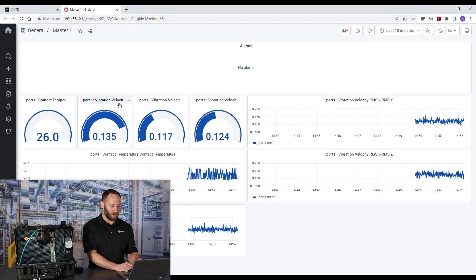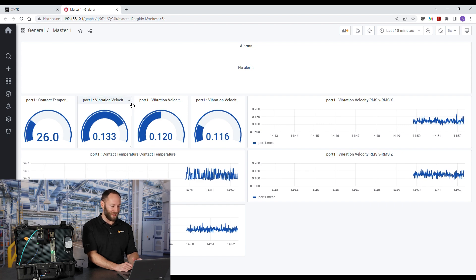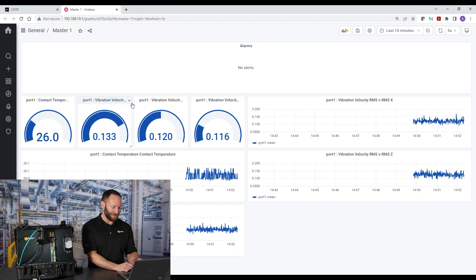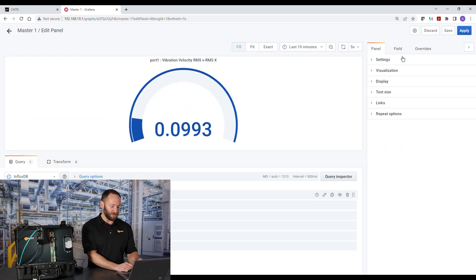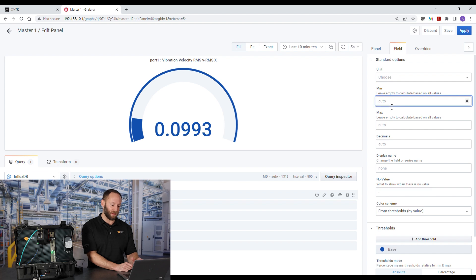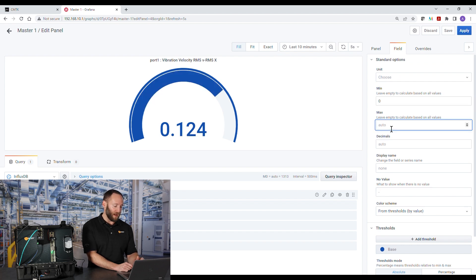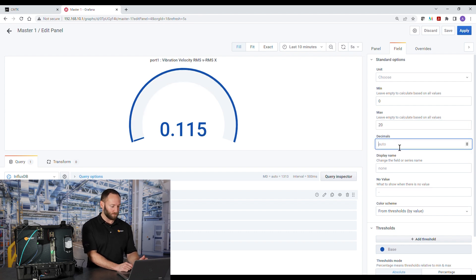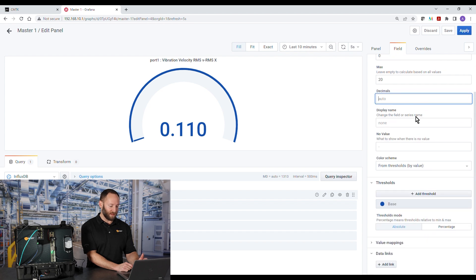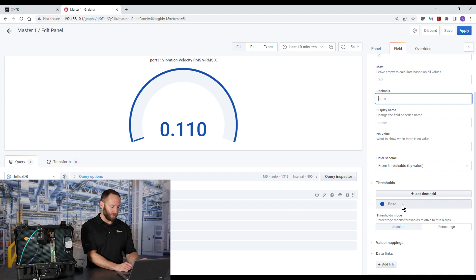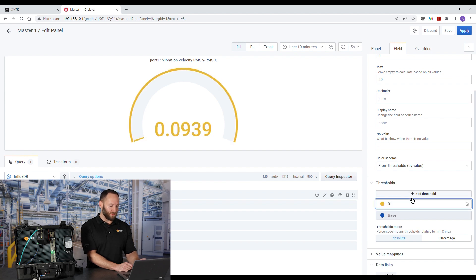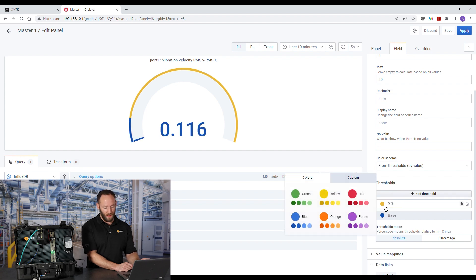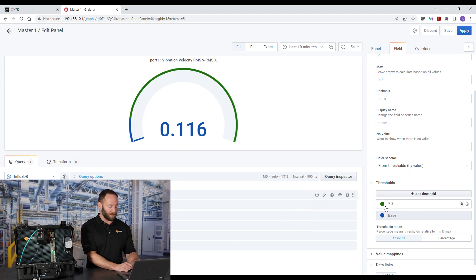The first thing we're going to do is edit vibration velocity RMS on the X axis. We'll use drop down menu, select edit, and then the field tab, and then basically fix scale the gauge. So we'll specify a minimum value of zero and a maximum value of 20, which represents 20 millimeters per second. Once we fix the scale, now we want to add thresholds. We'll leave the blue for the baseline, which we'll call severity zone A. We'll add severity zone B, which the threshold was 2.3 millimeters per second. And that color is going to be green.